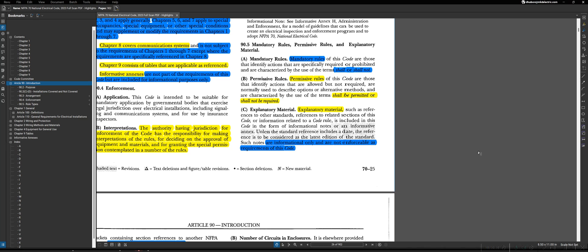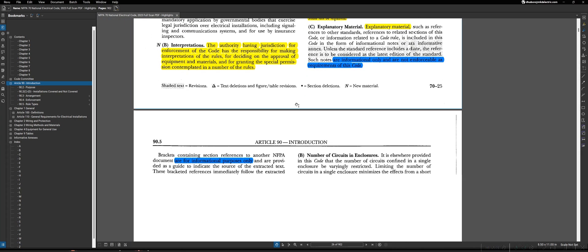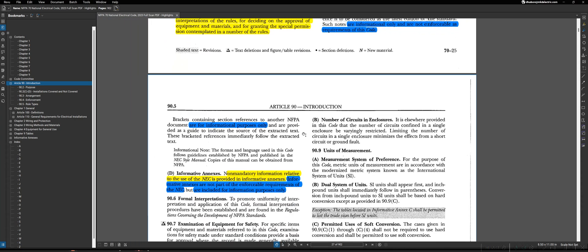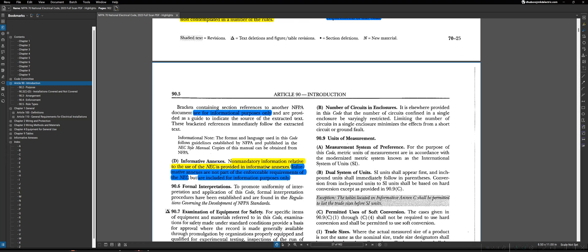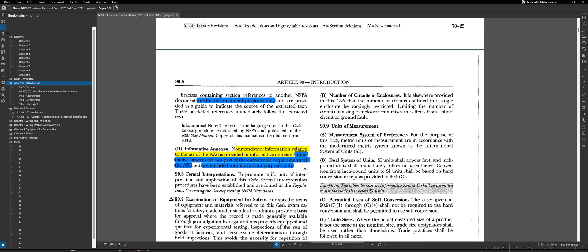The last type of NEC subject that we have is explanatory material. Explanatory material is only included, as we can see here, as an informational note, essentially. It's just for reference or for your favor, you could say. It is not an enforceable rule of the NEC, and there are many instances in which this is often thought to be a rule and enforced when, in fact, it's actually not. The NEC goes on to verify this multiple times. You can see here for informational purposes only. And once you go to the annexes, informative annexes are not enforceable, but for information purposes only. So these should not be taken as being a code requirement, but in many instances, they can help to explain things or provide references that are helpful.